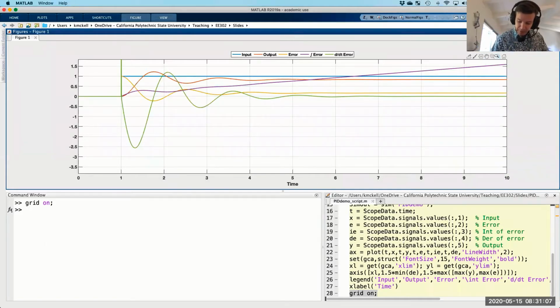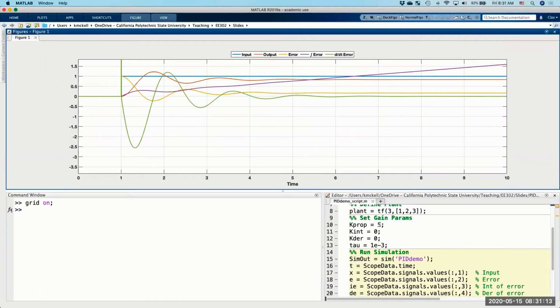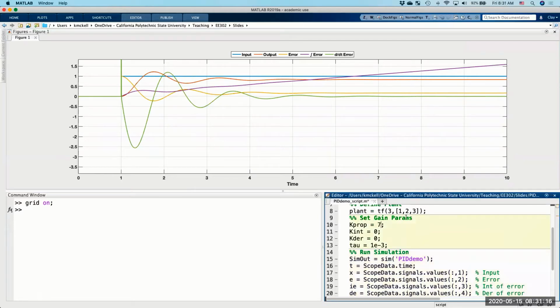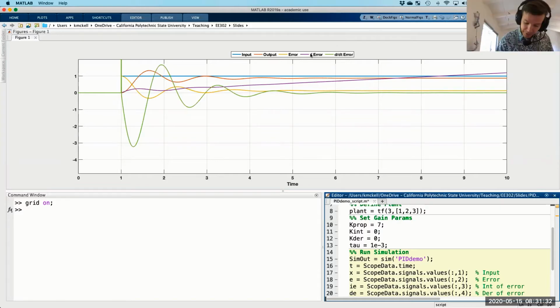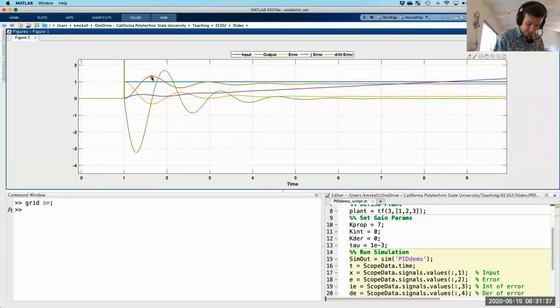I mean, we can fiddle with it a bit more if you're not convinced. So maybe we can set this up here to 7. The second hump is going to be the one we use to determine whether or not it's quarter amplitude decay, so you need both the first and the second hump. Right, because you're trying to measure this height as about 4x this height.